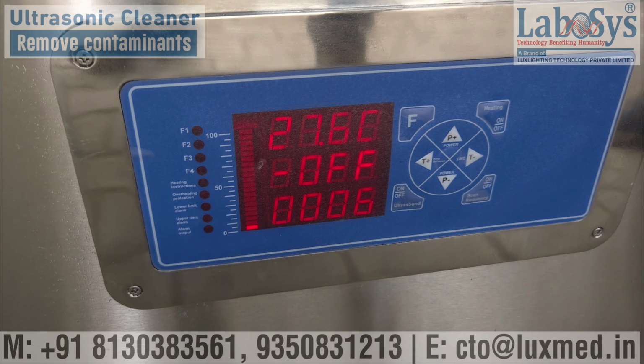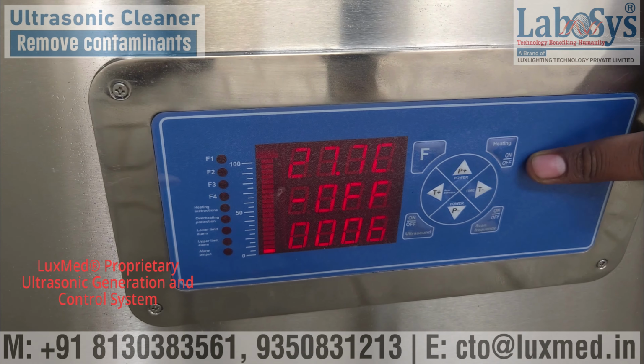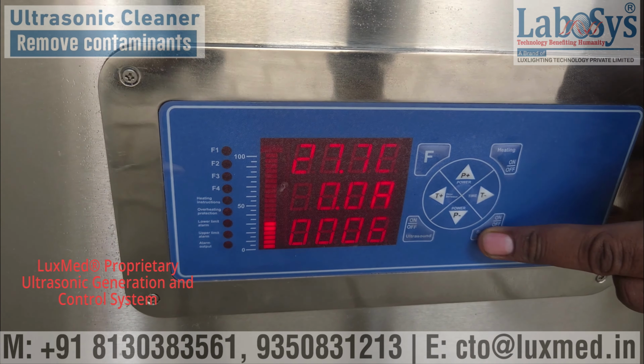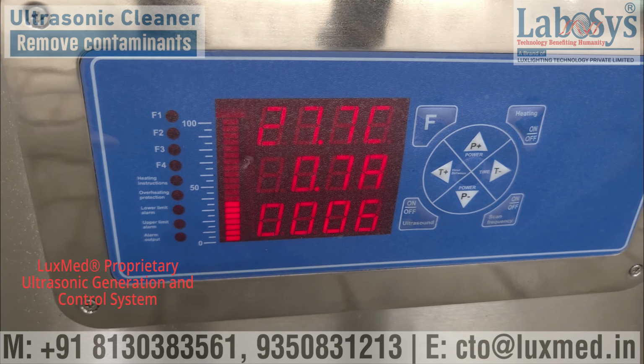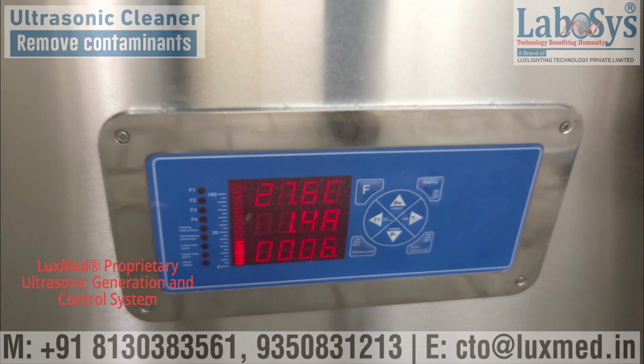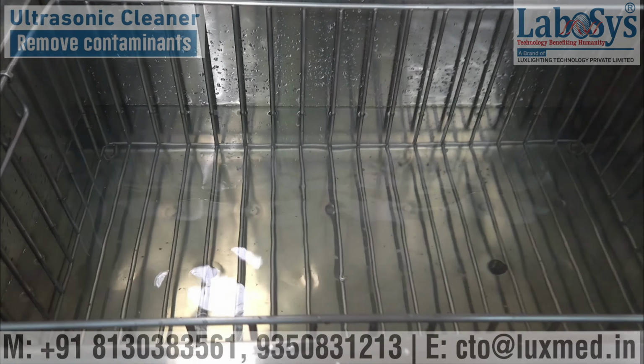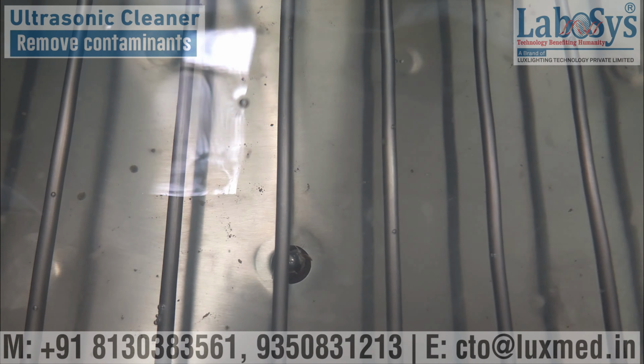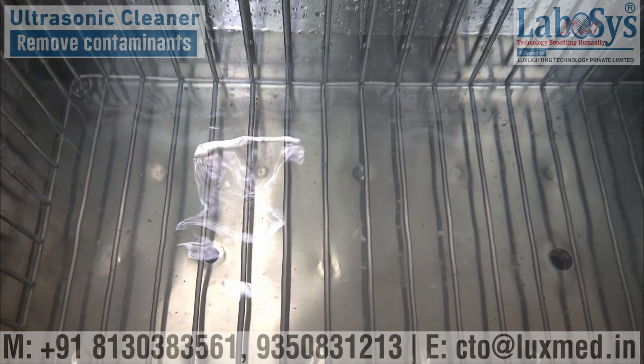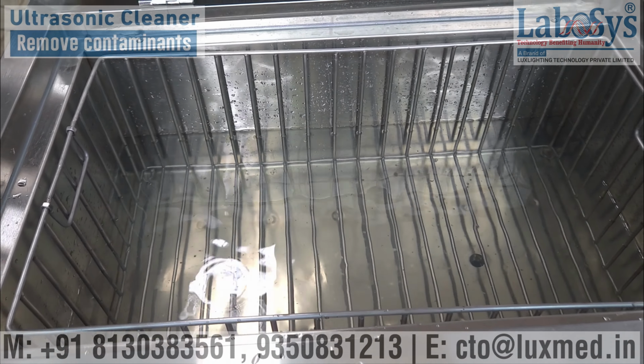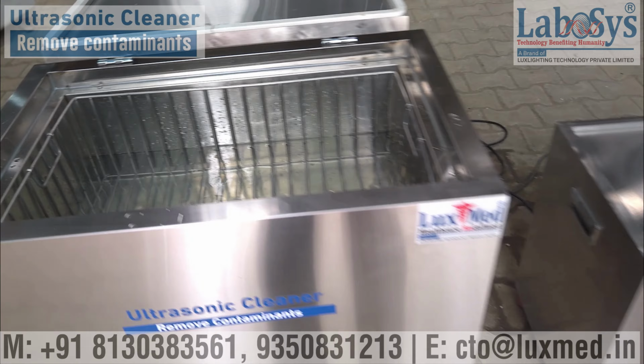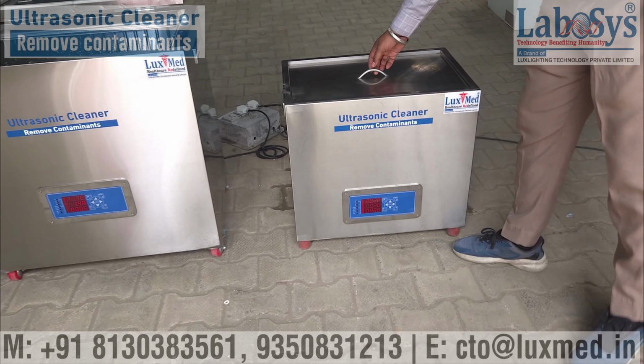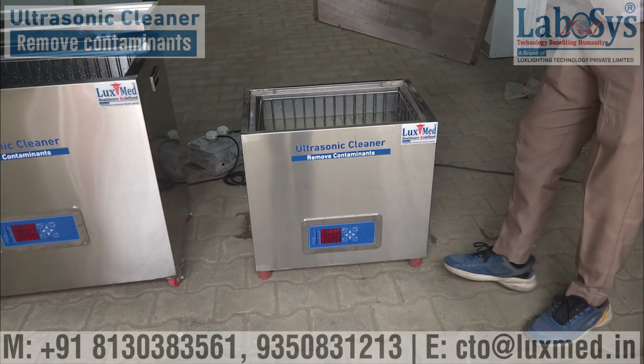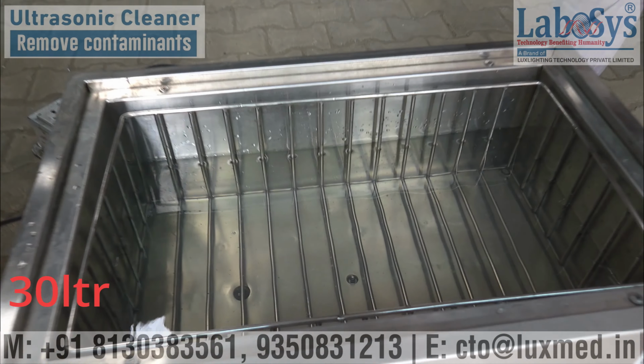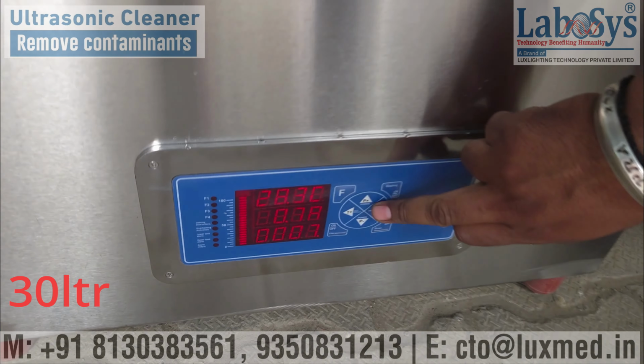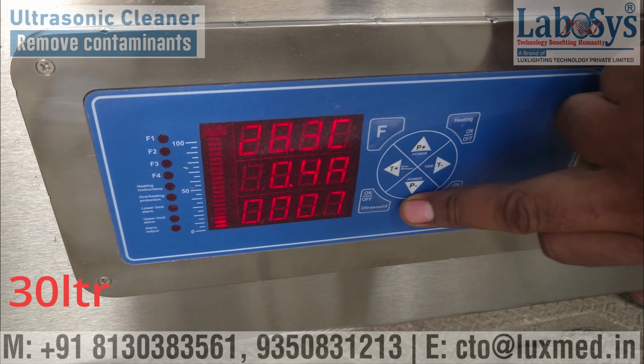3. Bubble collapse and shock waves. As the sound waves continue to pass, the pressure fluctuations cause the cavitation bubbles to expand and contract rapidly. Eventually, the bubbles collapse violently, implode, generating localized shock waves, high temperatures, and intense pressure. 4. Cleaning action. The shock waves and high temperatures dislodge dirt, grease, and other contaminants from the surfaces of objects immersed in the liquid. The cleaning solution can also help to dissolve and remove contaminants.